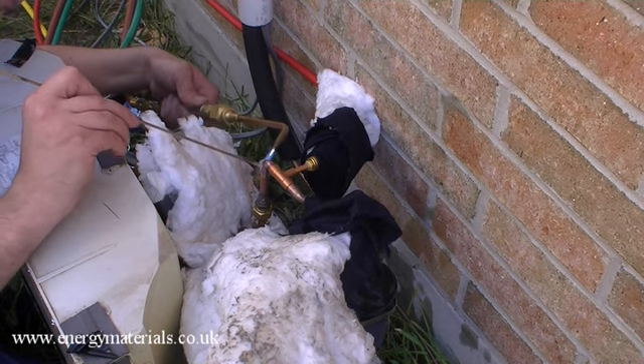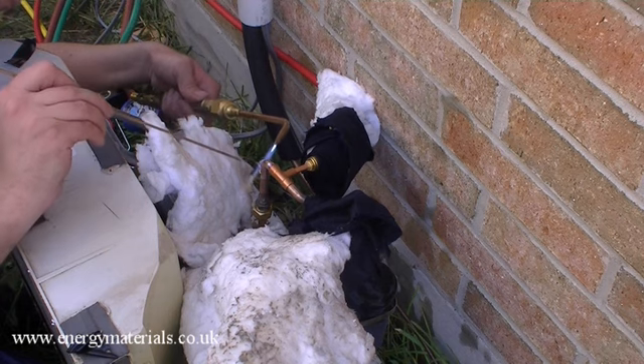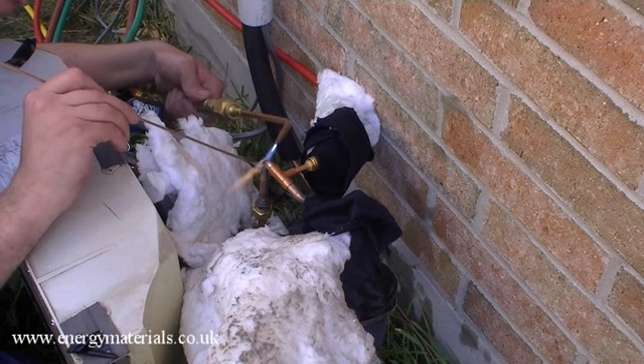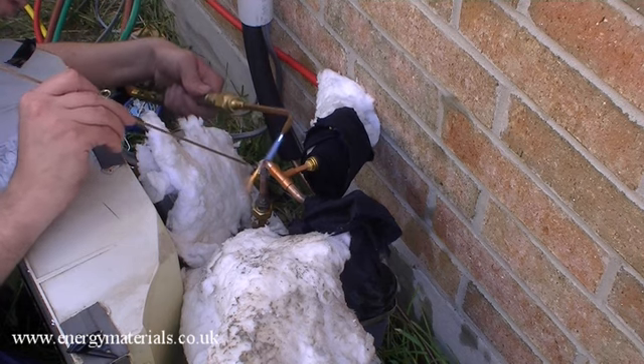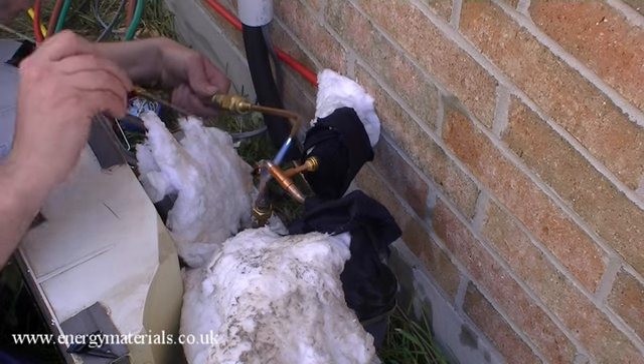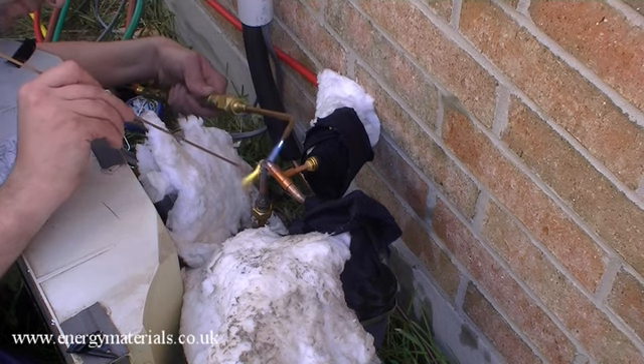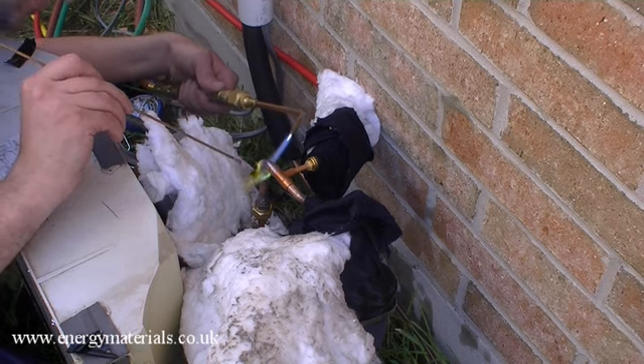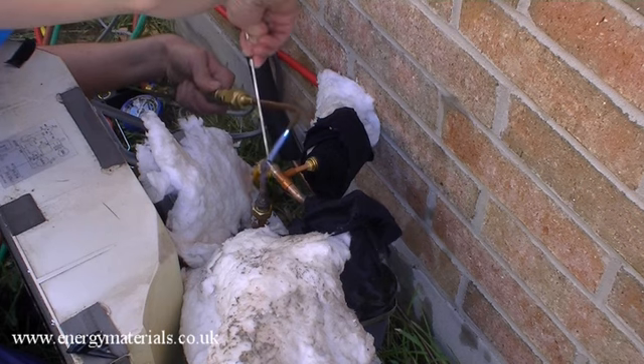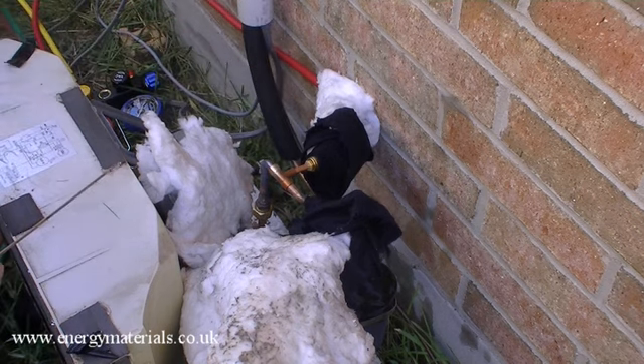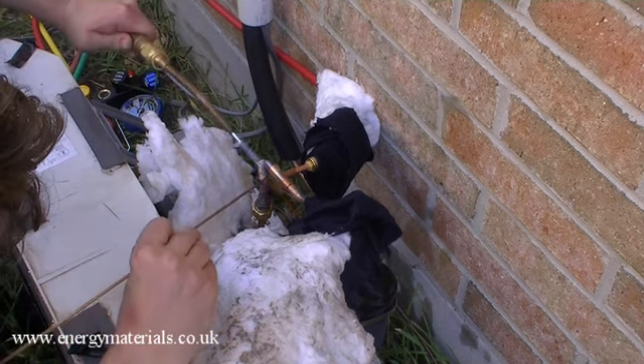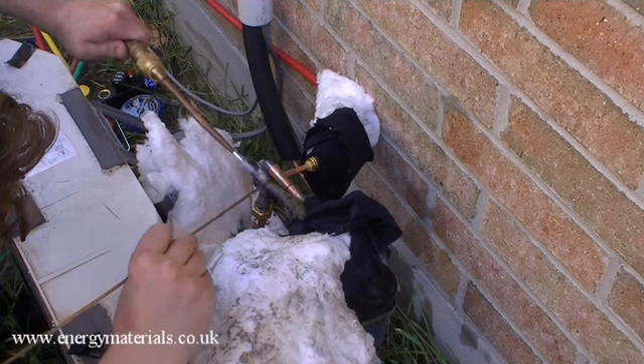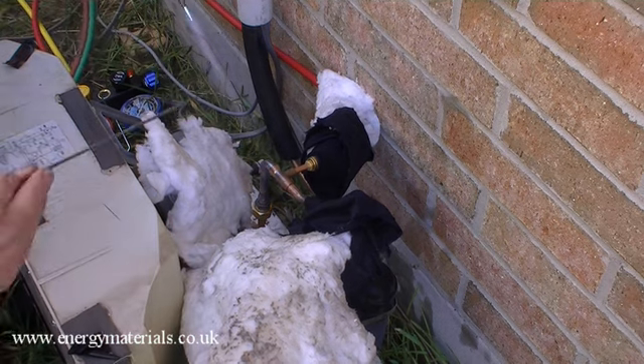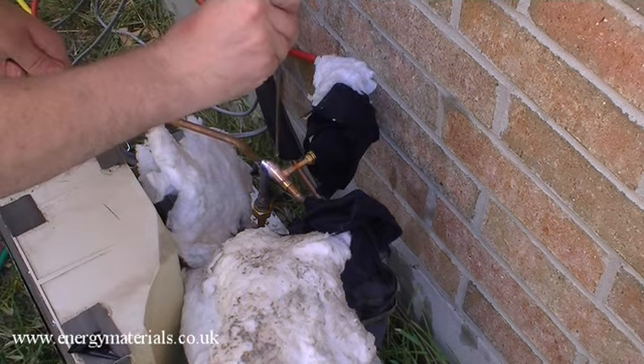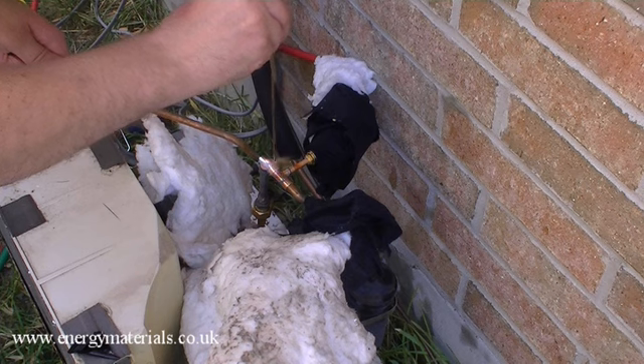And now we're going to braze the line set together. To do this, we're using a copper, phosphorus, silver alloy as the braze metal. The advantage of this is that we're not going to use any flux. Flux could potentially introduce contamination into our line set. In this case, the phosphorus is basically acting as the flux. We also have a purge of inert nitrogen gas flowing through the line set. This prevents oxidation on the inside of the copper tube.